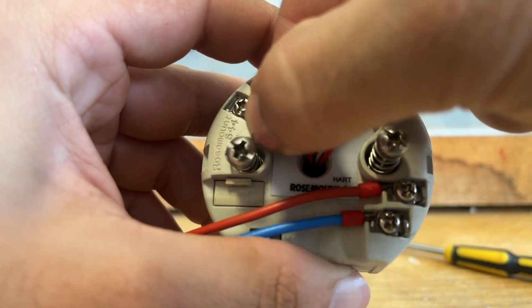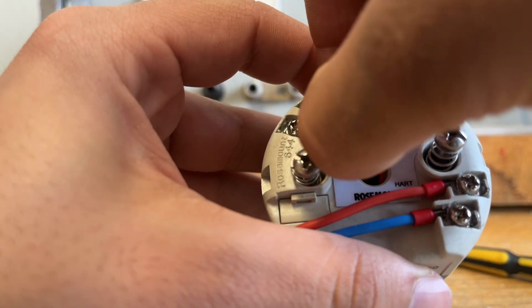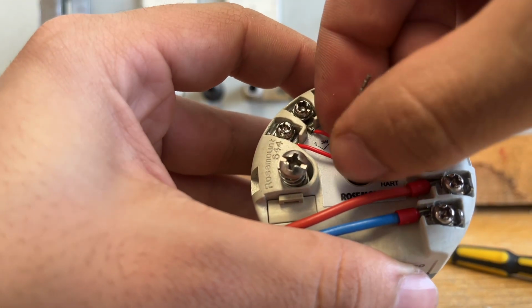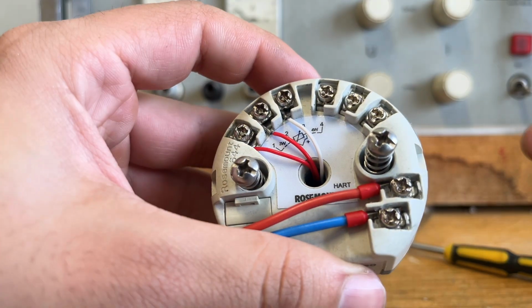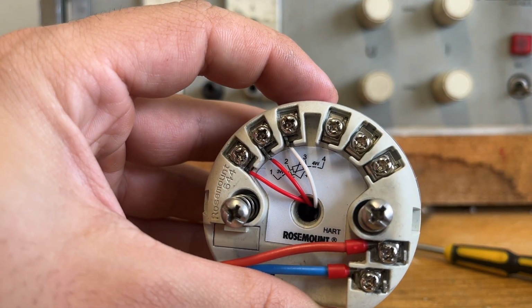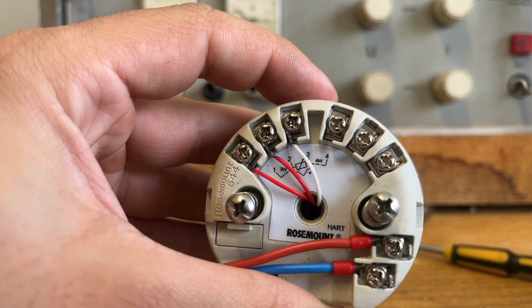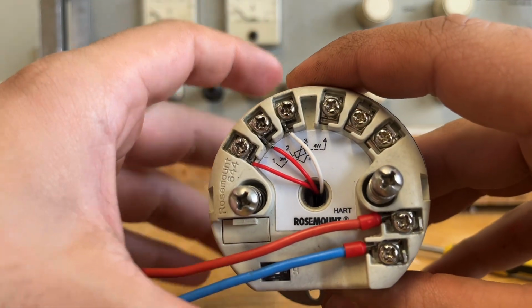I'll connect the first red wire to terminal 1, the second red wire to terminal 2, and the white wire to terminal 3. Terminals 1 and 2 are common, which helps the transmitter compensate for lead resistance and improves accuracy. Now, to configure the transmitter, I'll connect my HART communicator.